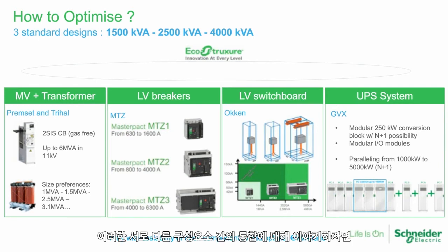If we speak about the integration between those different components, the idea here is really to do the mechanical integration, of course. So it's first the mechanical integration and the cabling integration between the switchboard and the UPS from the main switch, the main circuit breaker, but also to the distribution. So that can be done also for integration of busways downstream to be able to have the preliminary integration before shipment.